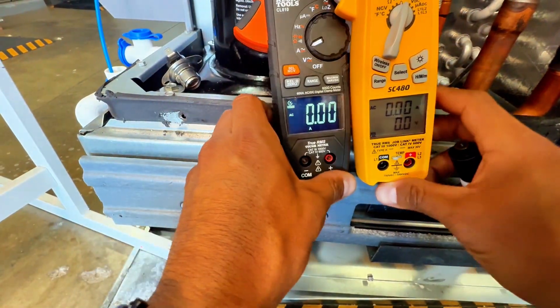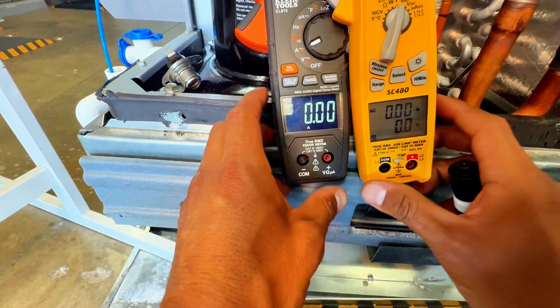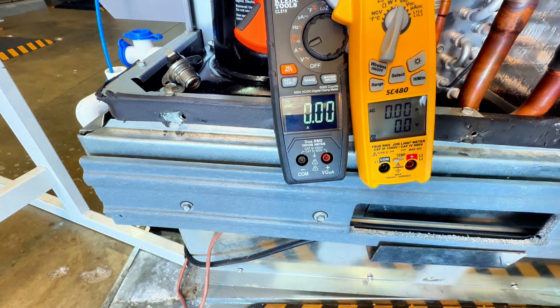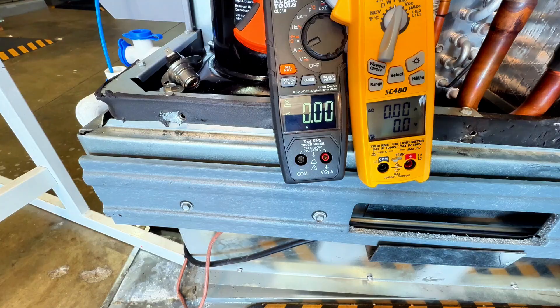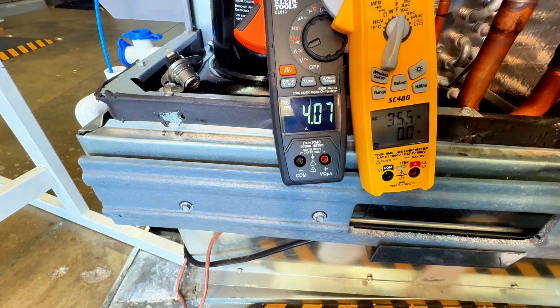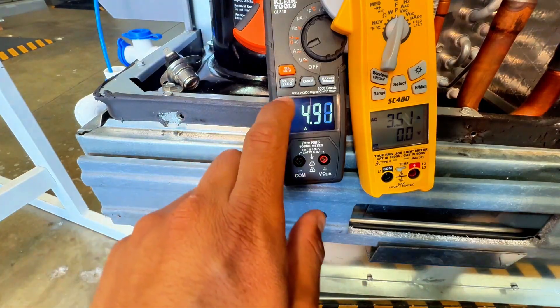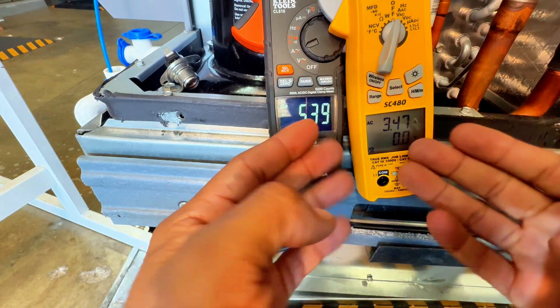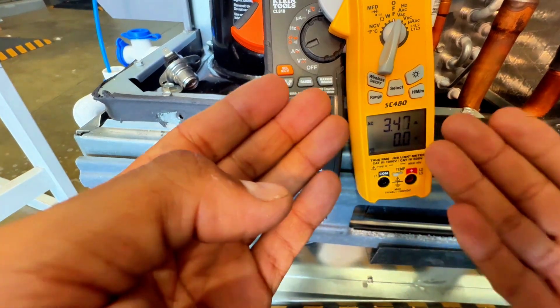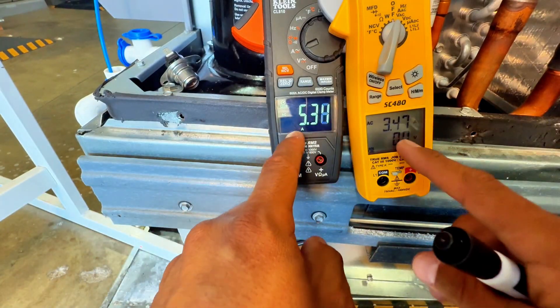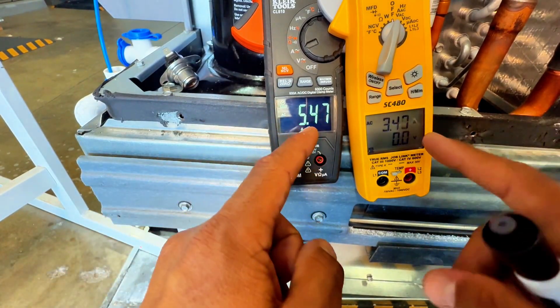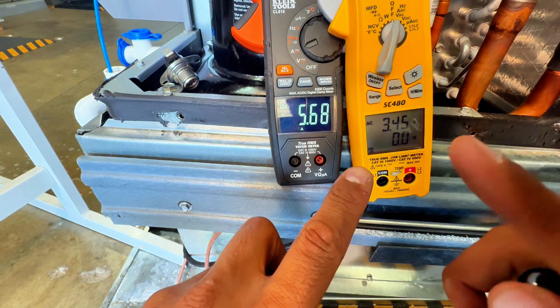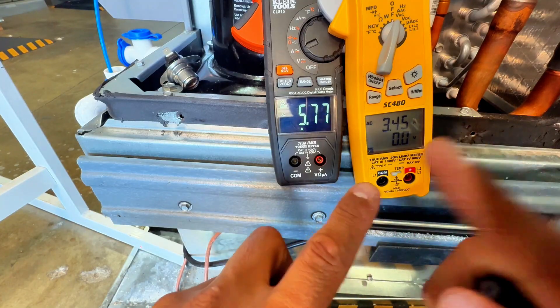Okay, so I have everything already set up. I already identified my wires. This blue one is my start winding. This blue one goes to the capacitor on the Herm, which is right there. So I've identified that one. And then this clamp here is on the yellow one, which goes to my run, my R, and the black one's common. So this black one, if you were to follow that into the compressor, into the pin, there is a thermal overload switch that is in series with that to protect the compressor. So, but we have everything already set up. I got my, we're going to be able to check the run winding and the start winding.